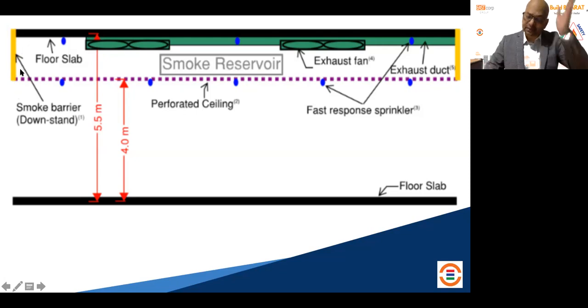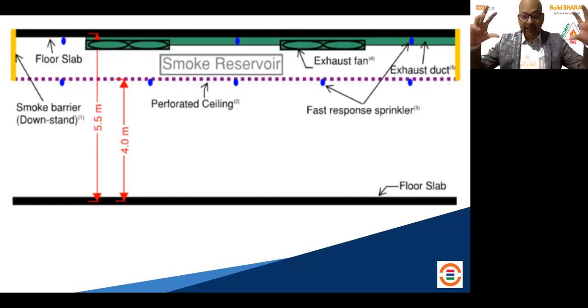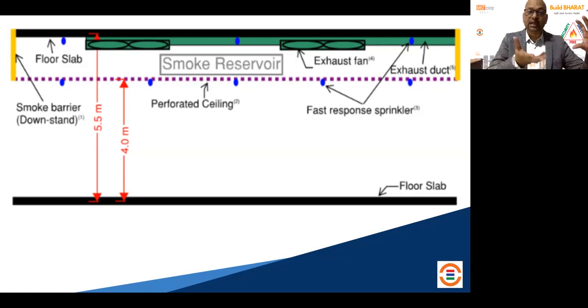This is basically a downward projected structure which is fire rated. By creating that downward structure, the smoke, which has a property to go up all the time, the moment it hits the main ceiling, will horizontally find space. The moment it hits a smoke barrier, it will take time to confine that area and will not go to the adjoining area. So how do you achieve that smoke compartmentation? By creating the smoke barriers.